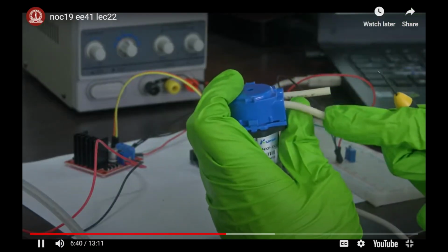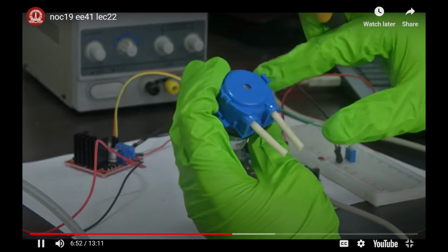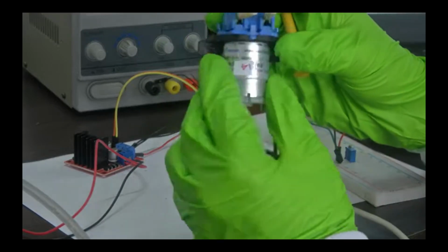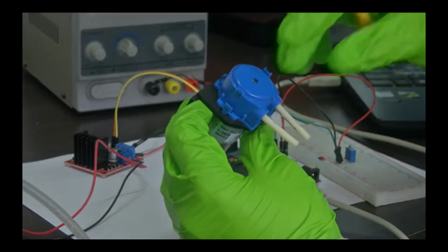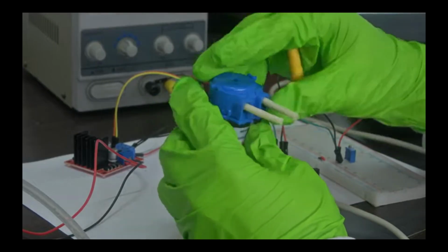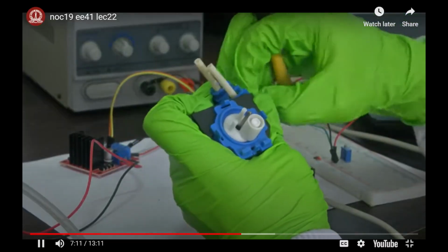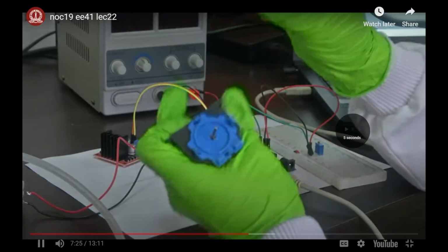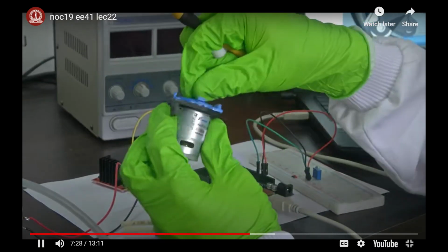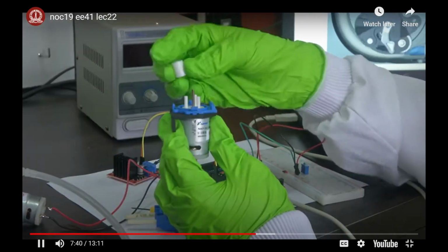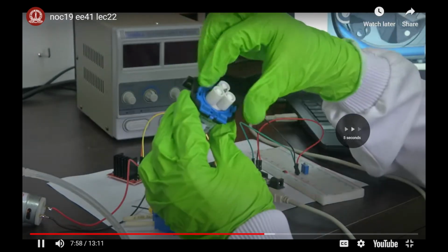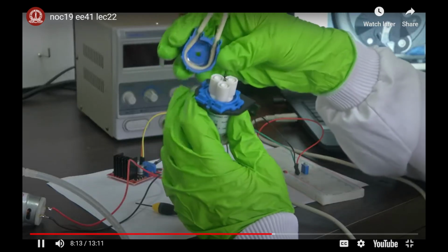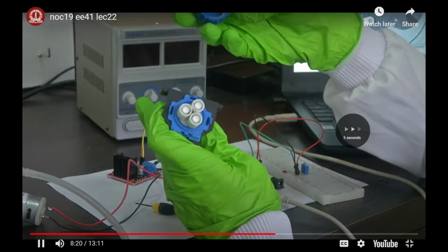If we give the input fluid in, it will come through this tube, and you can see there is nothing but a DC motor here. The DC motor is what rotates the roller that I showed. There are rollers here. You can see the tube over here, and there is a motor, like what you saw in the GIF. This roller unit will start to rotate. So this is the internal.